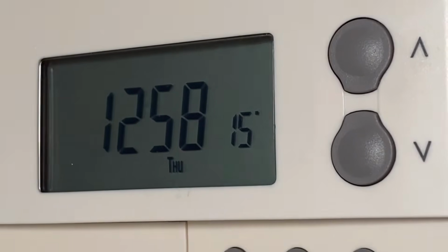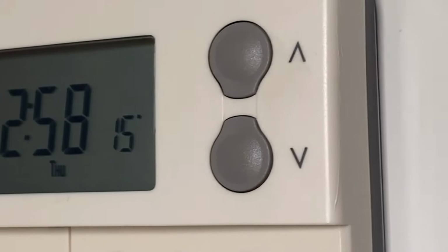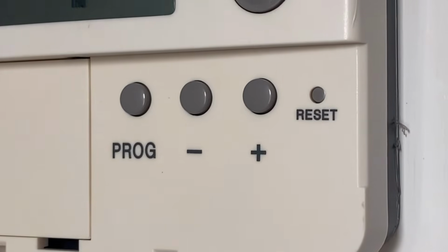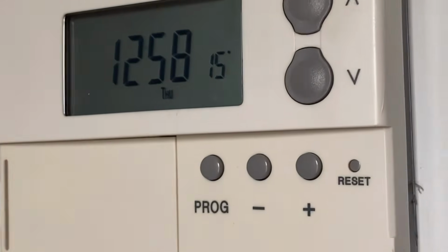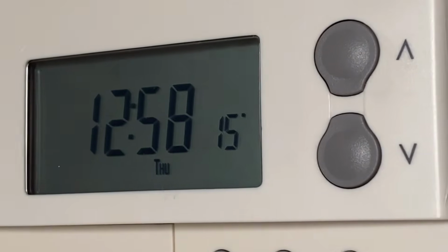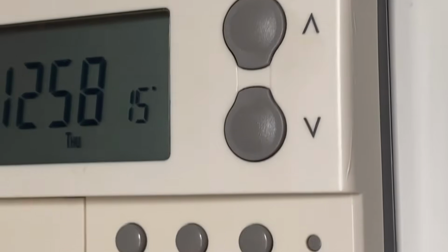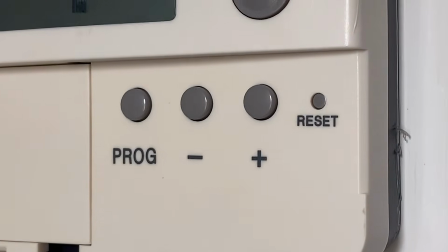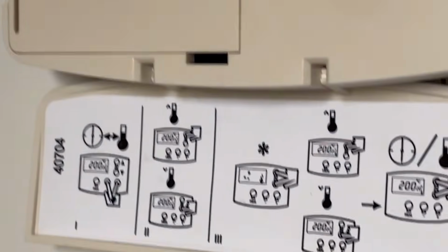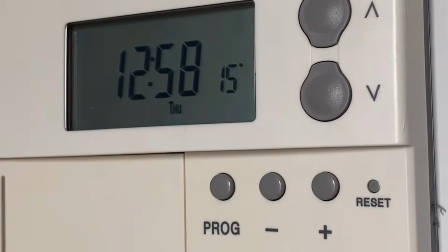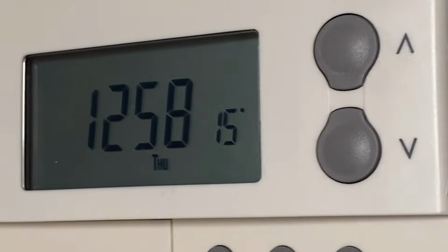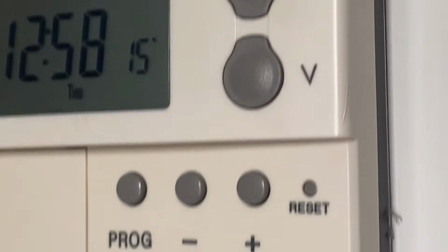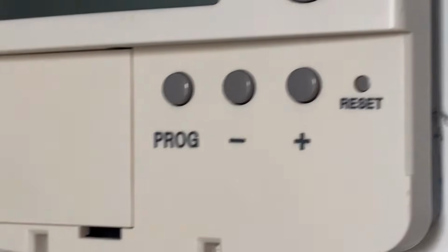Please note that turning your thermostat to a higher setting will not make your room heat up any faster, as how quickly your room heats up depends on the design of the heating system, variables like the size of your boiler and radiator. And in the same breath, the setting doesn't affect how quickly your room cools down. So basically, when you program your thermostat to a lower setting, it will result in the room being controlled at a lower temperature, and as a result giving you savings on energy.